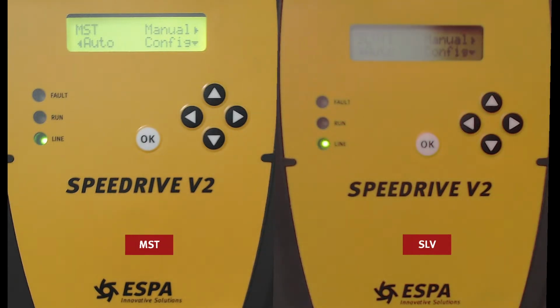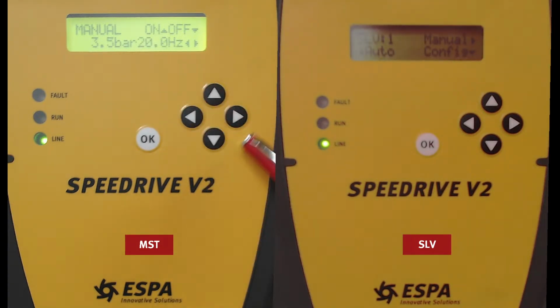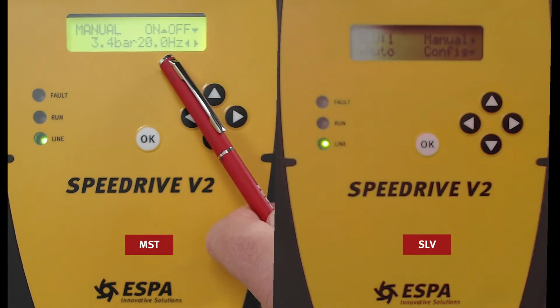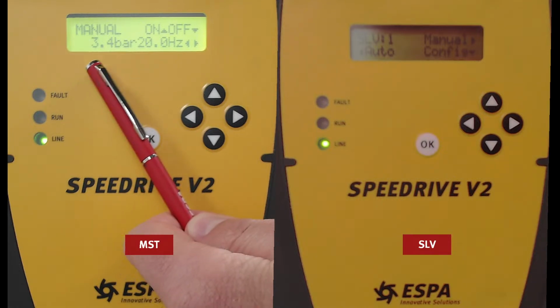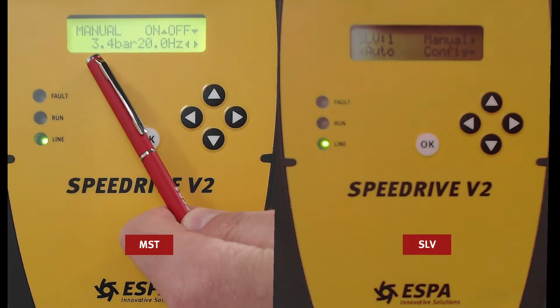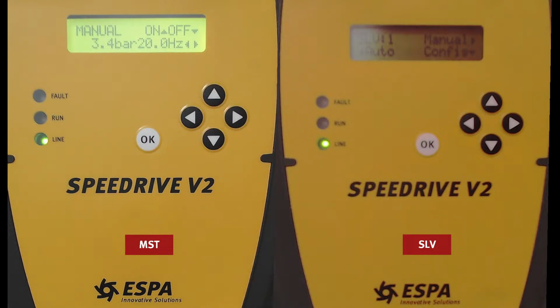One of the first things that we can do is go to manual and see if the pumps are turning correctly, clockwise, normally with our motors. Other motors could be anti-clockwise, but our motors turn clockwise. So if we go up, we will turn on the pump at 20 Hertz. And this is the pressure that we have right now in the system, 3.4 bar. So let's start manually.